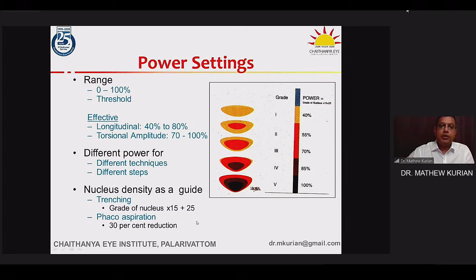Delivering power for a beginner, the quality of foot pedal control may not be so great. So you could go with what is called a panel mode, where you have a preset maximum, and from the beginning of foot position 3 to the end of foot position 3, you are at the same amount of power. As you get more confident with the machine, you could go into a linear or surgeon control mode where you can start position 3 at your preset level of 0 or the threshold and finish it at your preset maximum.